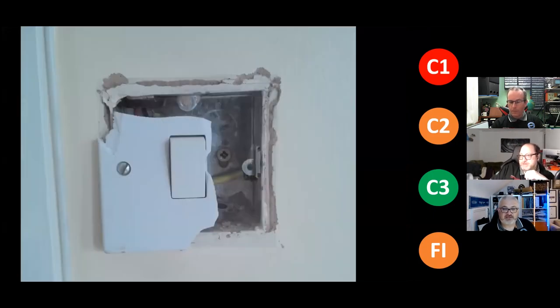Yep. Now there's a nice one. Broken switch. C1. Yeah, live parts. I'm going to do it just so that we can check. Yeah, it's all C1s. Fantastic. We're in agreement. C1. Direct, good access to live parts.